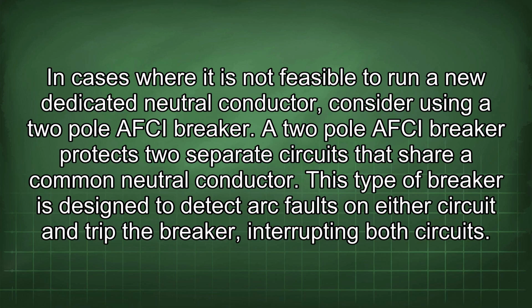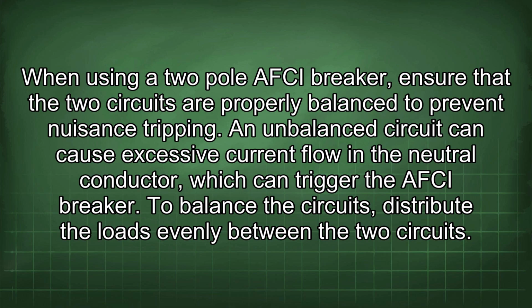In cases where it is not feasible to run a new dedicated neutral conductor, consider using a two-pole AFCI breaker. A two-pole AFCI breaker protects two separate circuits that share a common neutral conductor. This type of breaker is designed to detect arc faults on either circuit and trip the breaker, interrupting both circuits. When using a two-pole AFCI breaker, ensure that the two circuits are properly balanced to prevent nuisance tripping. An unbalanced circuit can cause excessive current flow in the neutral conductor, which can trigger the AFCI breaker.